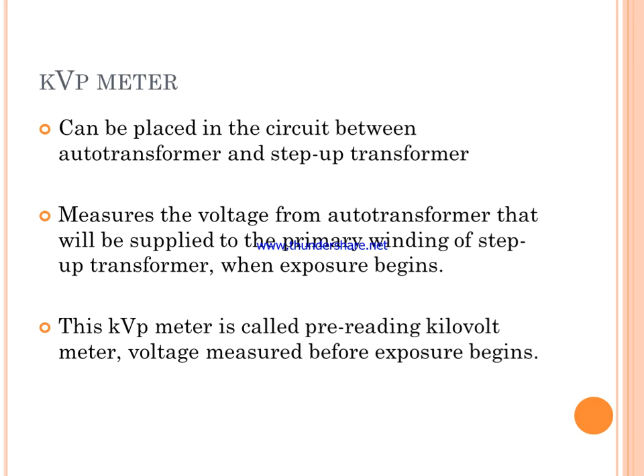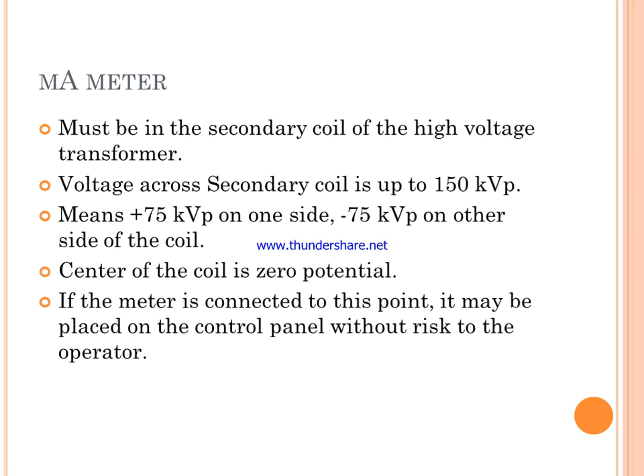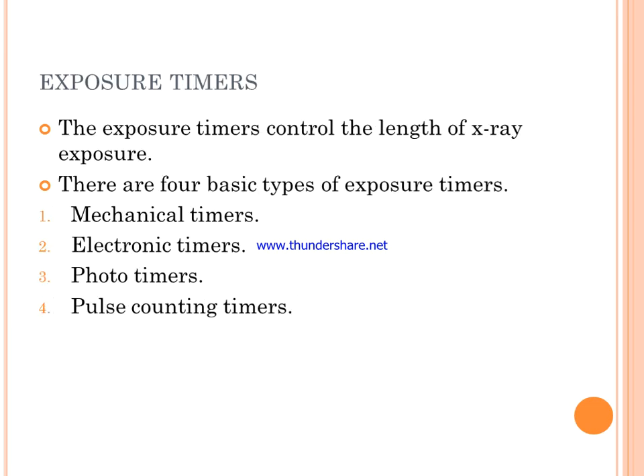The kVp meter measures the voltage from the auto transformer that will be supplied to the primary winding of the step-up transformer when exposure begins. It is also called a pre-reading kilovolt meter, measuring voltage before exposure begins. The mA meter is connected to the secondary coil, which is up to 150 kVp — plus 75 kVp on one side and minus 75 kVp on the other, with the center of the coil at zero potential.